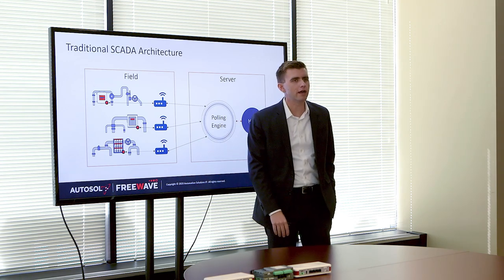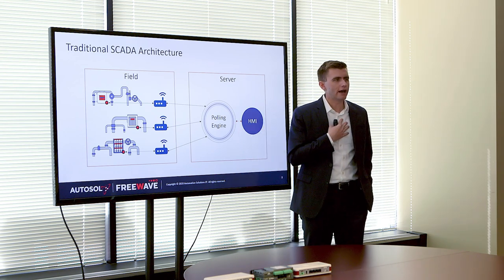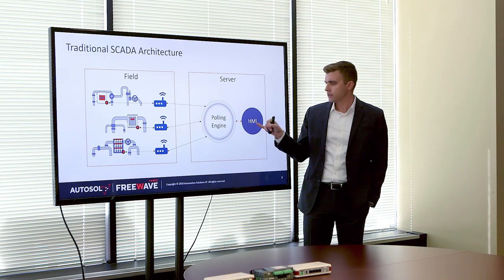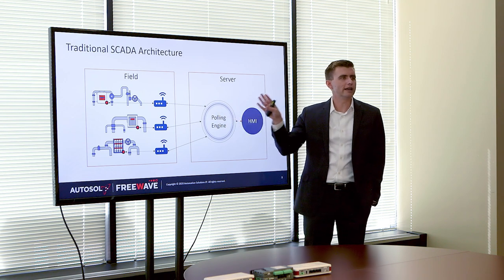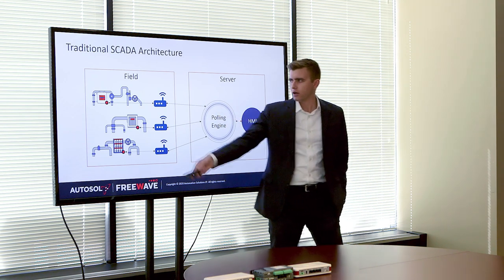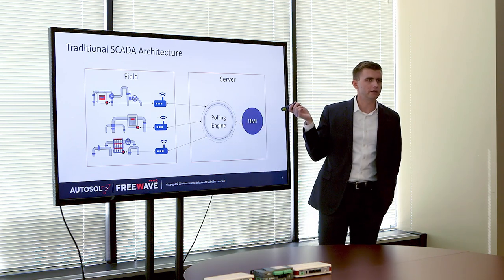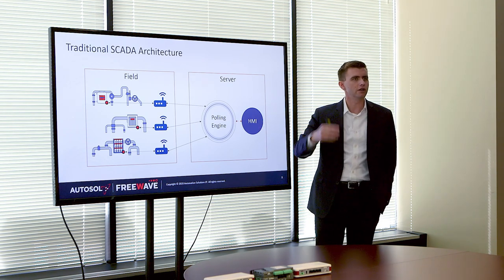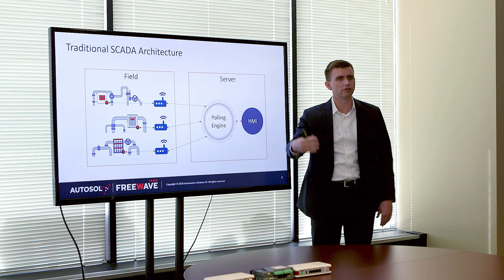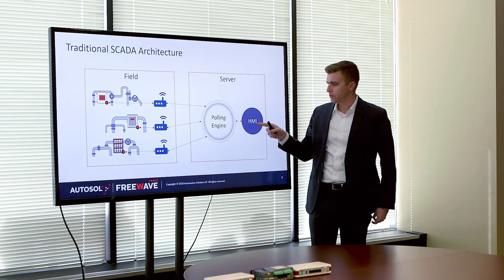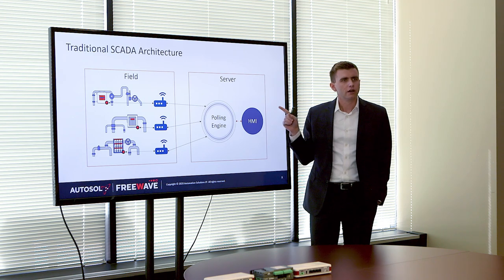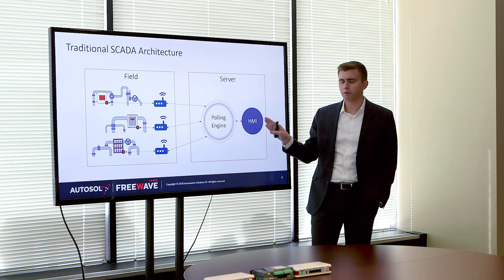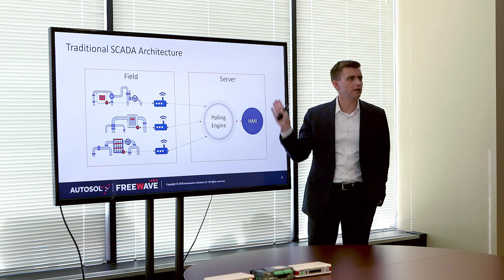He's still going to use a hundred percent of that bandwidth. And because the HMI is where field data becomes contextualized and gains value — let's say a total flow sends a value of 1,500 back up to the HMI — well, 1,500 what? This is where it gets context: oh, this is 1,500 PSI on a very important piece of my infrastructure at a river crossing. So the HMI gets burdened as the only source where all this data is stored, and has to serve both operators for safety and production as well as other business units.